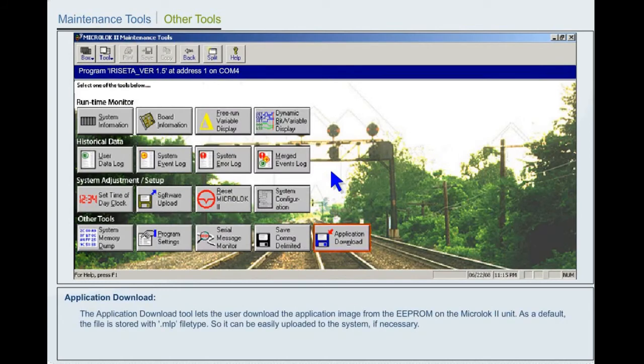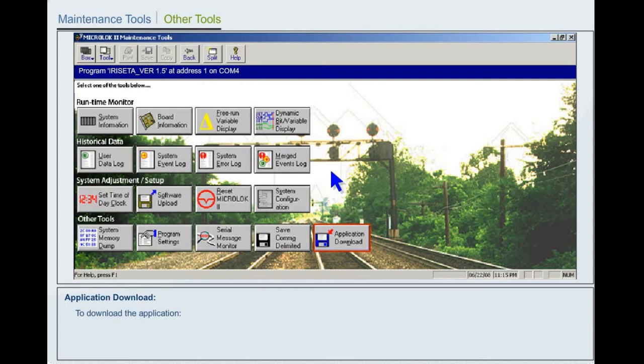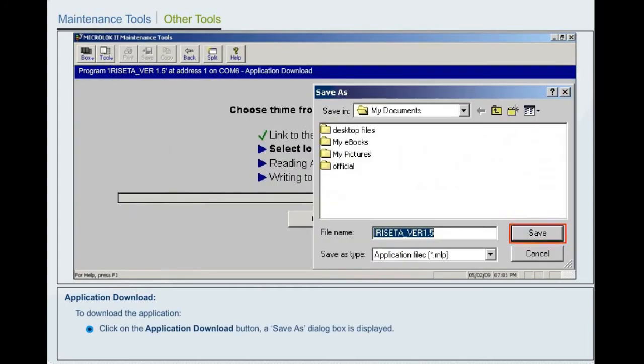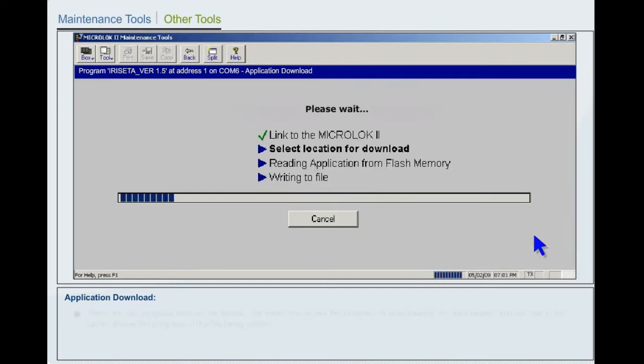Application Download. The Application Download tool lets the user download the application image from the electrically erasable programmable read-only memory on the MicroLok II unit. As a default, the file is stored with Microlock programming file type, so it can be easily uploaded to the system if necessary. To download the application, click on the Application Download button. A Save As dialog box is displayed. From the Save As dialog box, select the appropriate file and click on the Save button.